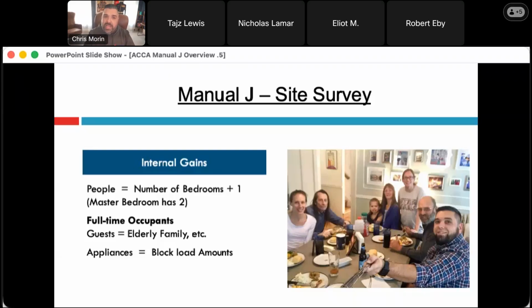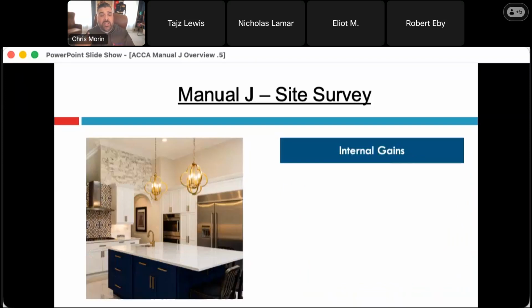Now, when we talk about appliances, also giving off heat within the building, there's some standard scenarios that are built into the software, and this is where I see a lot of people short themselves. If you're doing a block load, don't just use scenario number 1, which is enough for your kitchen. So refrigerator with a range is 1200 BTUs per hour. That's always the default in most software. If you're going to do a room by room load calculation, that's enough to put in the kitchen. You should be adjusting for others.